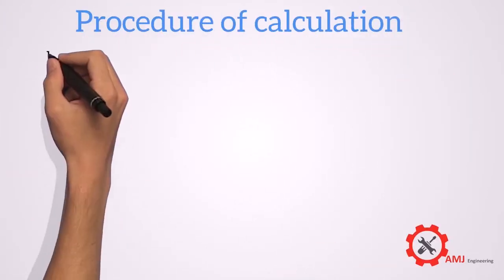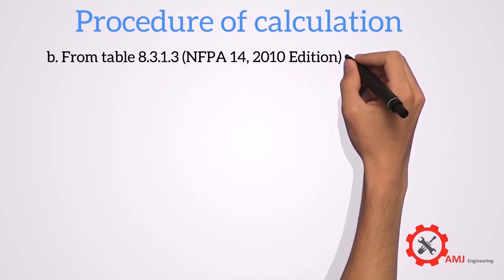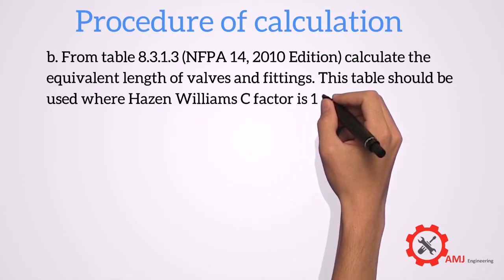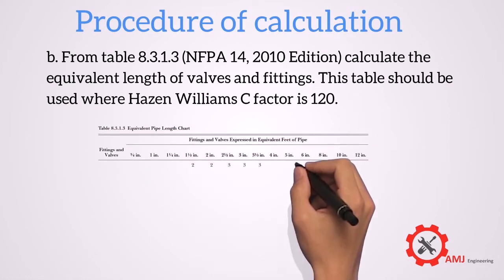From table 8.3.1.3 from NFPA 14, we can calculate the equivalent length of valves and fittings. This table should be used where Hazen-Williams C factor is 120.